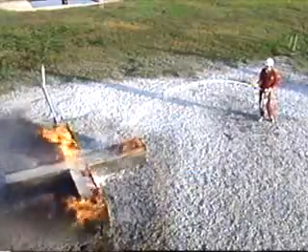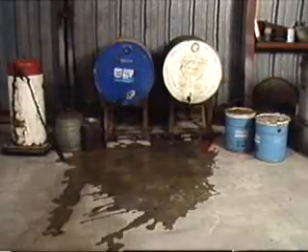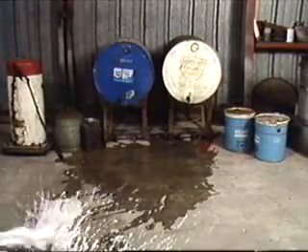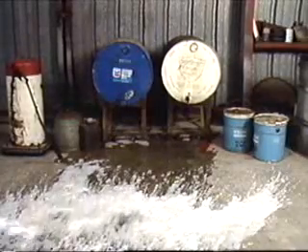If you are unable to play the foam off the back wall, you can spray the foam directly into the liquid. It is important, however, to momentarily divert the stream so the foam blanket can seal itself and completely cover the liquid. Another method for open container fires is to stand back and lob the foam so it falls over the fire. AFFF extinguishers are also used to prevent fires on flammable liquid spills — the foam blocks the release of vapors, preventing ignition.